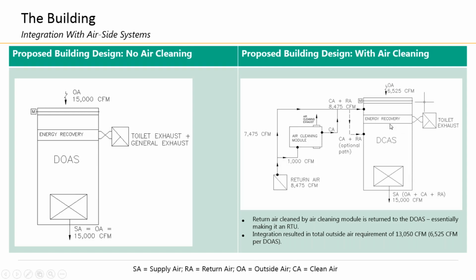Energy recovery in this case could potentially be eliminated under the ECB method. We're not below that 5,000 CFM number here, but your system should be efficient enough for you to completely eliminate energy recovery because it's only treating toilet exhaust at that point.